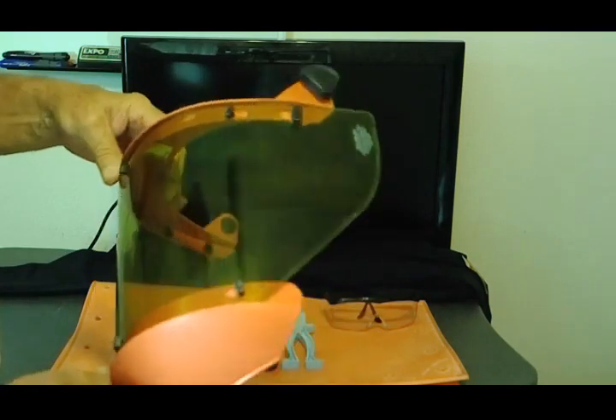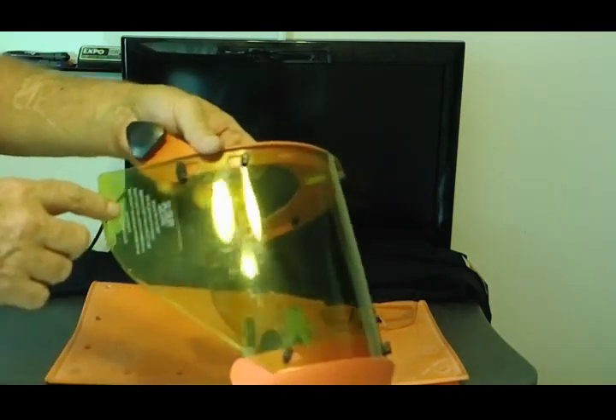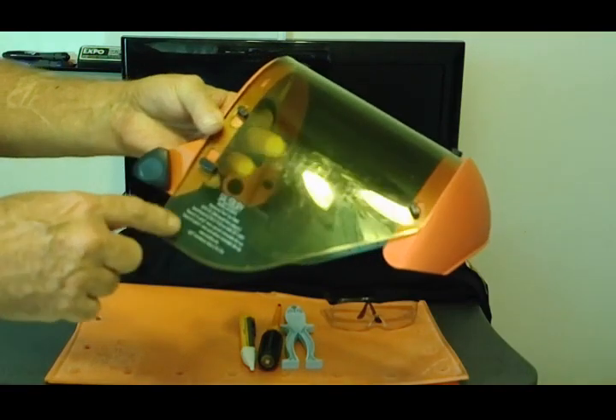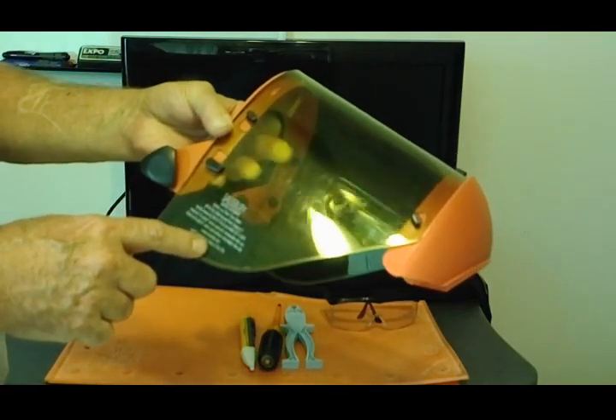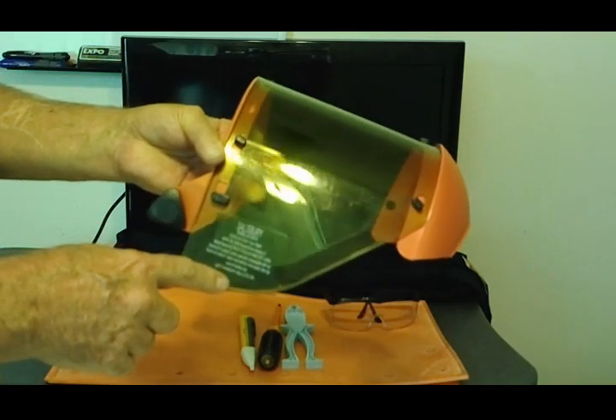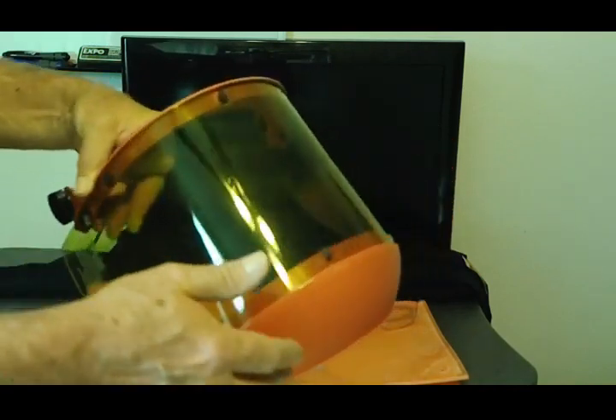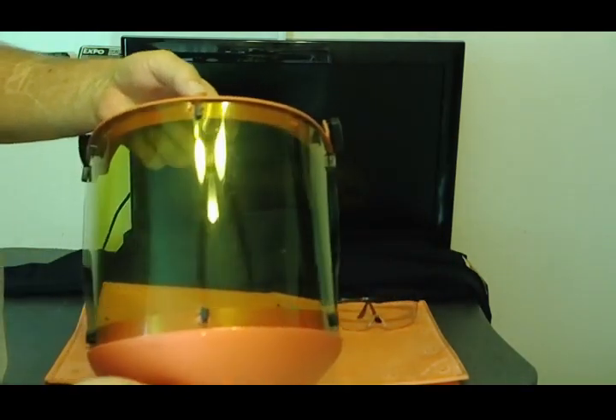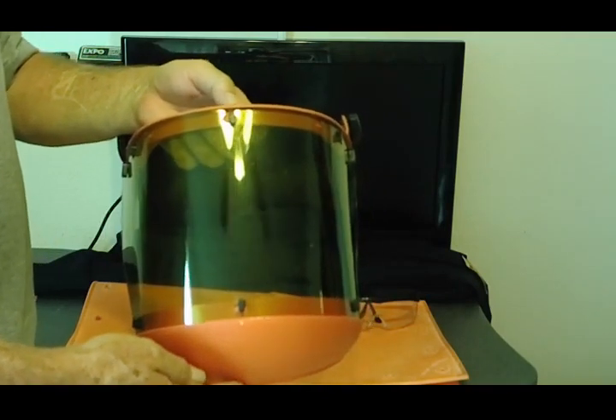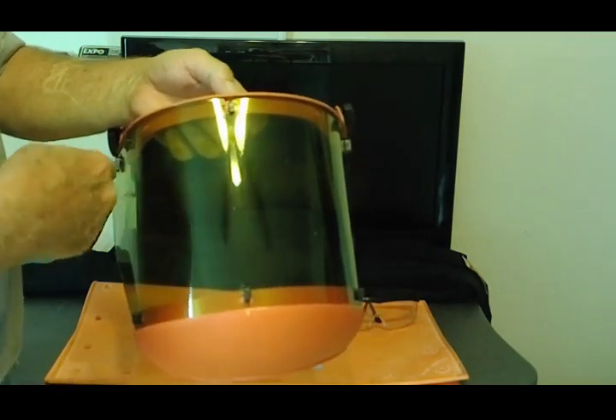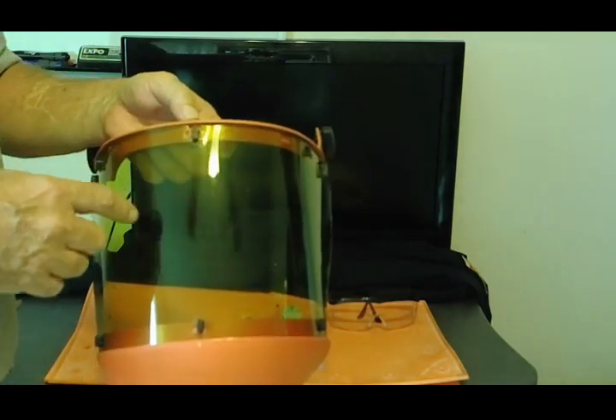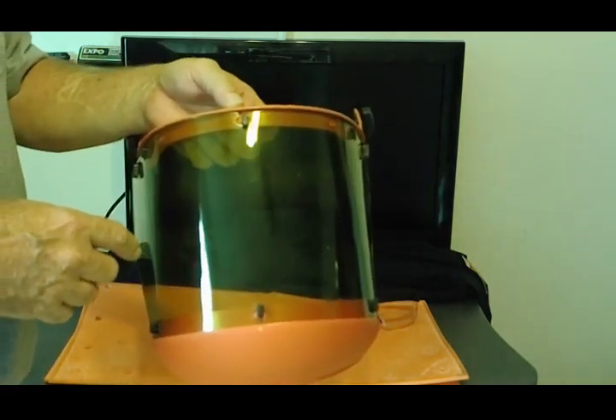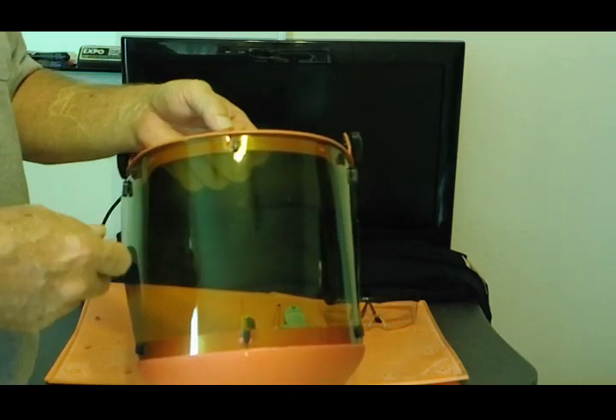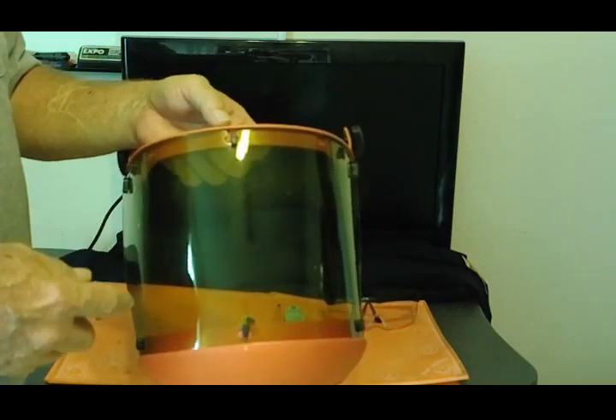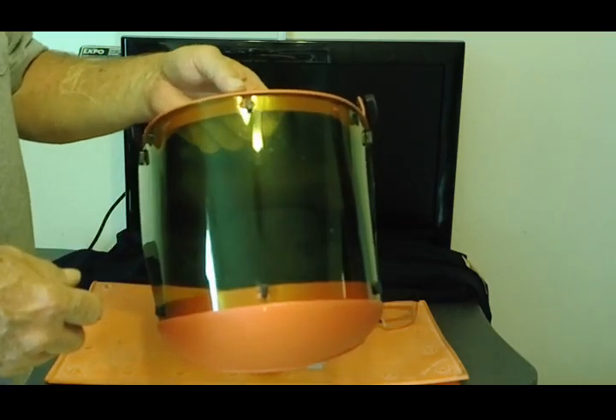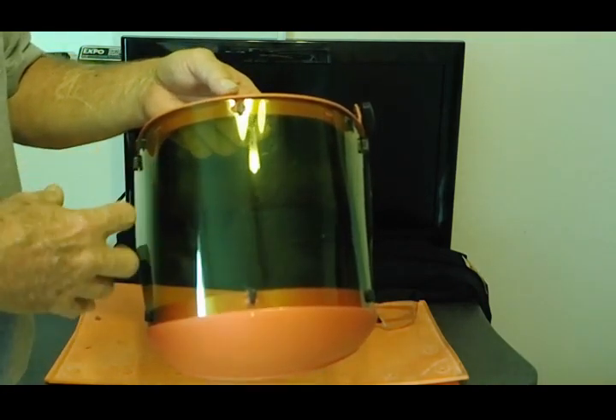So the face shields, the helmets, they all have to be rated. Now right here on the side, this face shield is rated up to 12 calories of energy. Now this is not a grinding shield, and a grinding shield is not an electrical face shield. This face shield is designed to withstand heat energy of up to 12 calories, that's all it's designed for. A grinding shield will not stop 12 calories; that grinding shield will melt to your face.